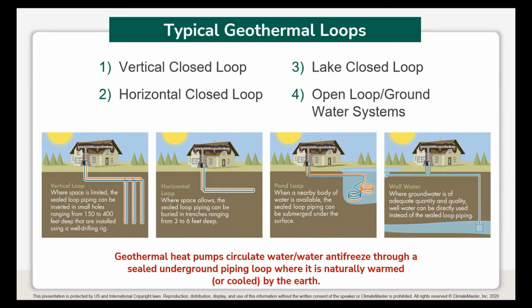Very common is vertical boring, where we have a drill rig that drills a 4.5 or 6 inch diameter hole in the ground to various depths, depending on the geology that the home is located in. And that is probably the most expensive ground exchanger that we could put in, because it does require expensive equipment to drill boreholes.